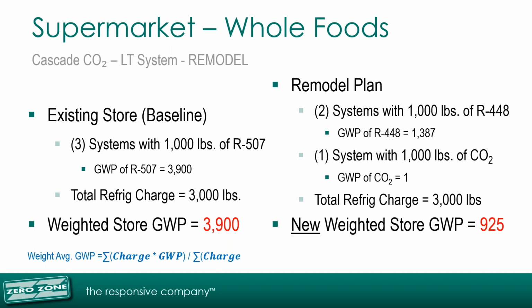In this example, the remodel plan allowed for the store's weighted average GWP to go from 3,900 to 925. I know this is only a single store example, and most retailers are dealing with multiple stores within their fleets. However, the moral of the story is that there are ways to lower your weighted average GWP significantly with the focus on your remodel strategy. I know each remodel has its own unique challenges, but there are strategies to meet or exceed the CARB requirements as seen in this example.